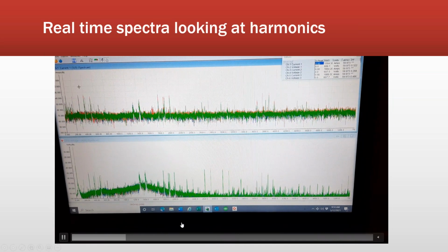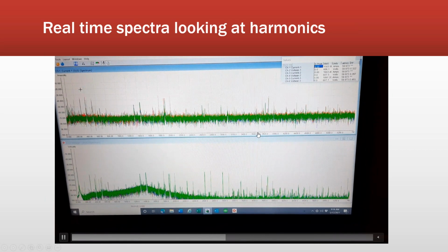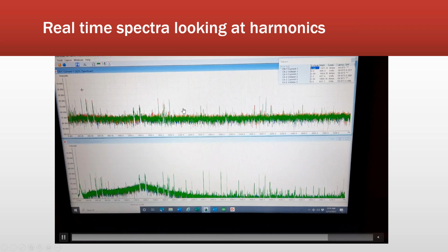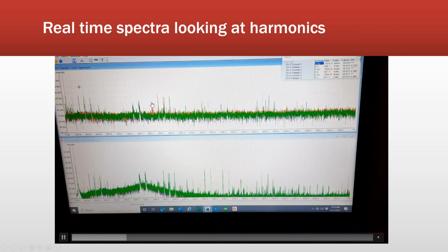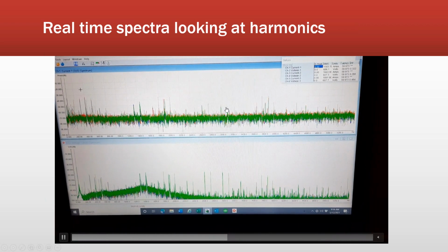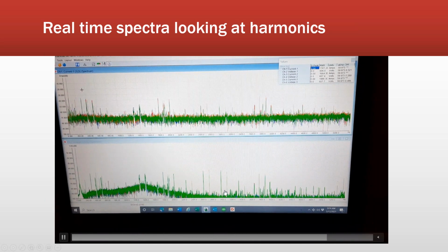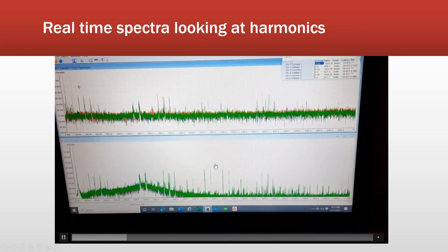If this comes through okay, this is a video of that tower that I just showed you, and just showing that the harmonic and the transformer signature, the firing signature of the drive, and the first harmonic of it, or second harmonic, I'm sorry, and the resonance signatures remain steady.